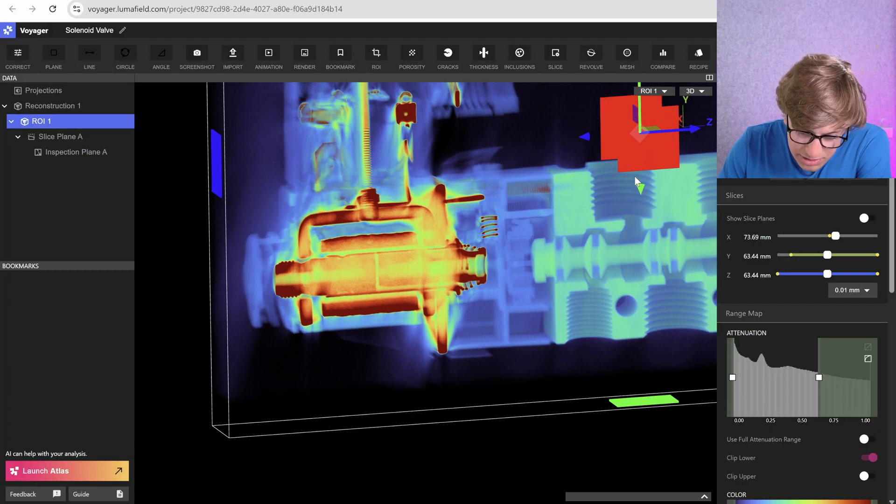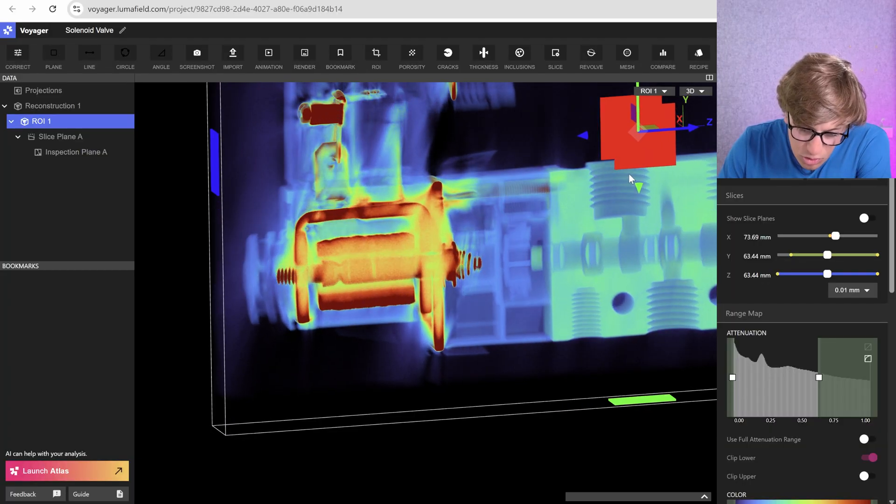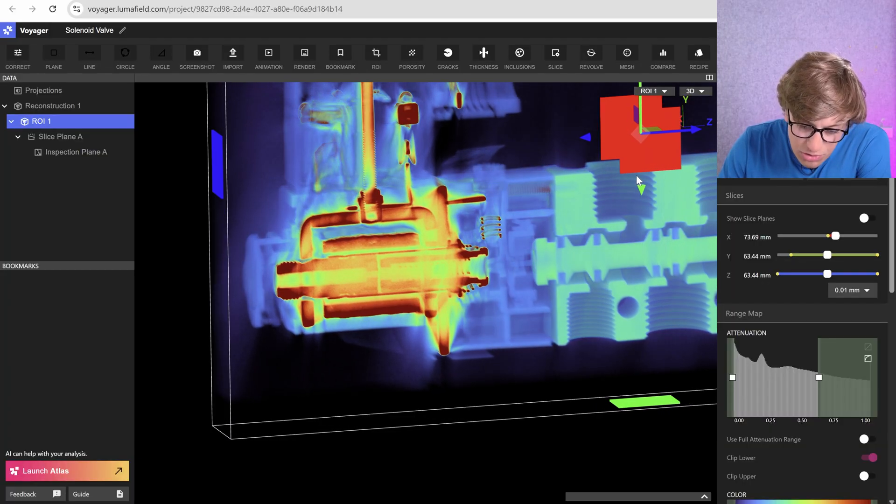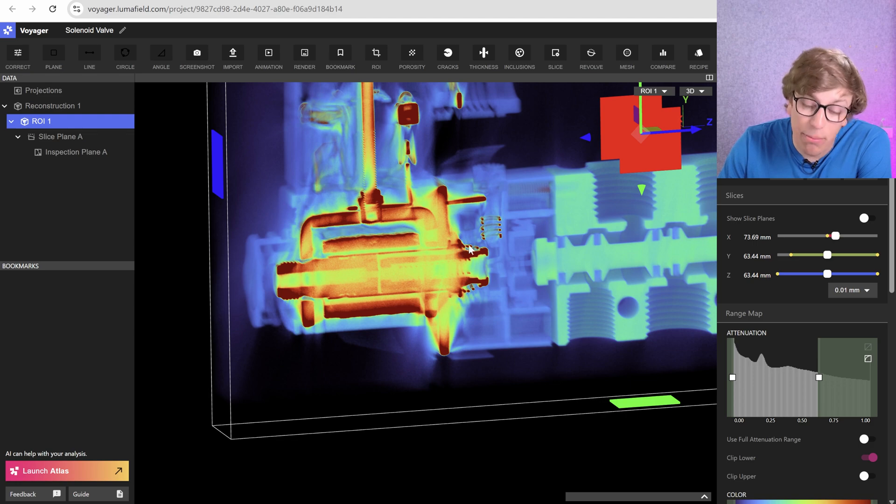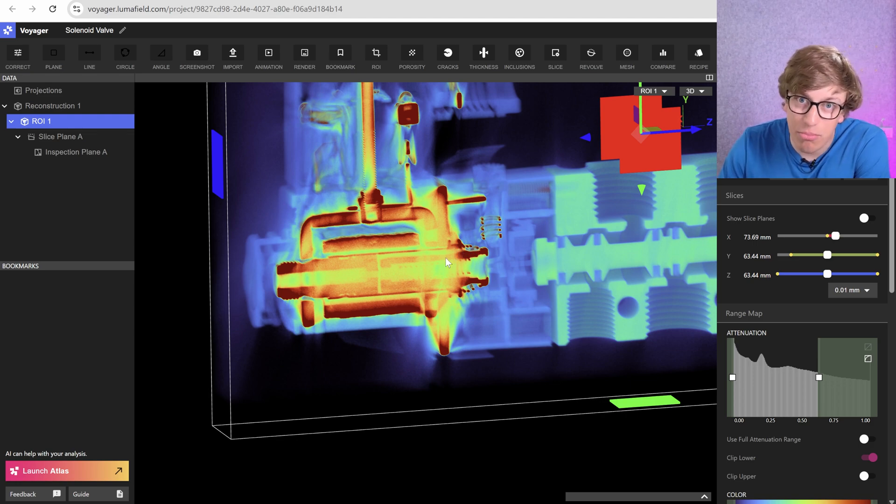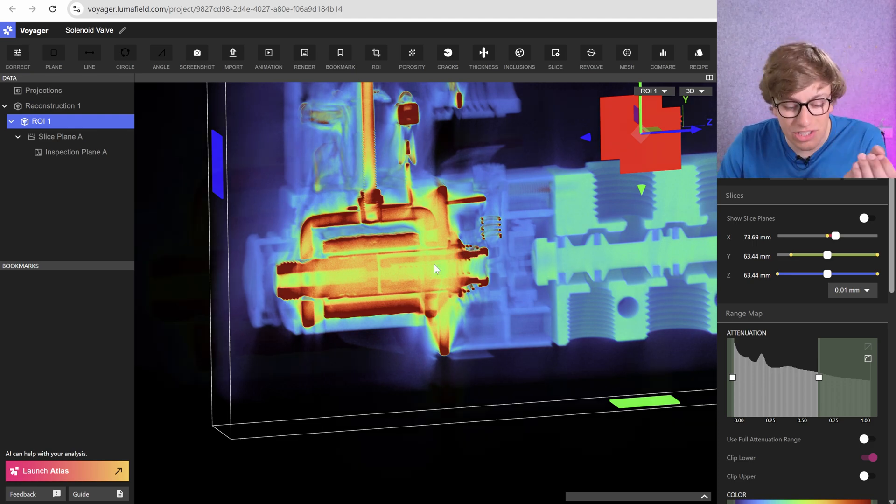Well, when this solenoid is pulled all the way back, it seals here. What that means is when the solenoid is pulled back because the solenoid is turned on—you're giving it electricity—it breaks this seal up front and high-pressure gas flows into this gallery.